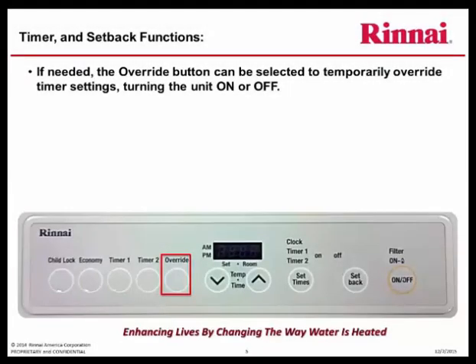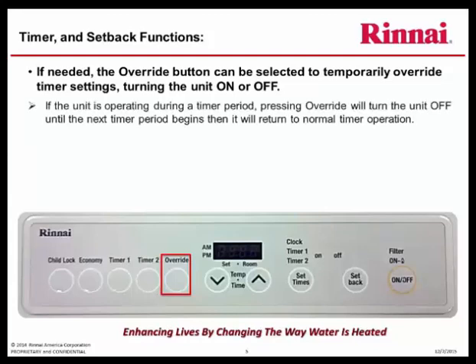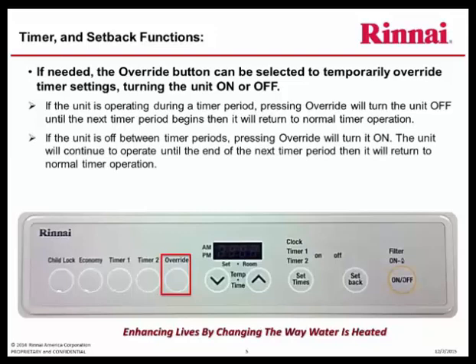If needed, the Override button can be selected to temporarily override timer settings, turning the unit on or off. If the unit is operating during a timer period, pressing Override will turn the unit off until the next timer period begins, then it will return to the normal timer operation. If the unit is off between timer periods, pressing Override will turn the unit on. The unit will continue to operate until the end of the next timer period, then it will return to normal timer operation. If Override is disengaged, the unit will resume regular timer operation.